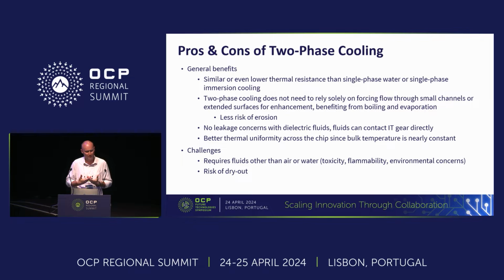We don't have to worry about erosion because we're using a lower flow rate due to the latent heat effect. We're using dielectric fluids, so even though in our solution we don't expect fluid to leak, if it does, similar to other forms of immersion cooling, it's not going to short out your electronics.